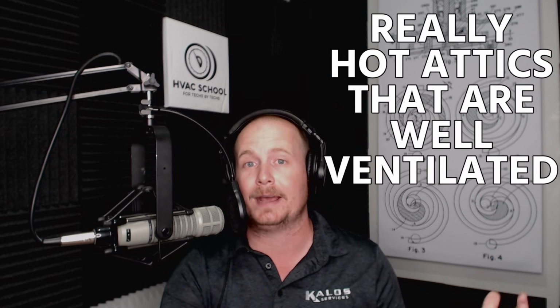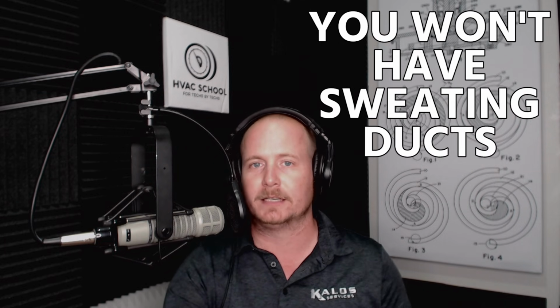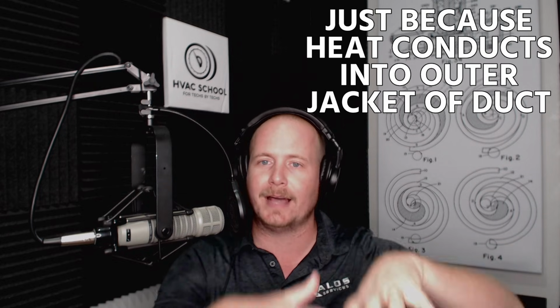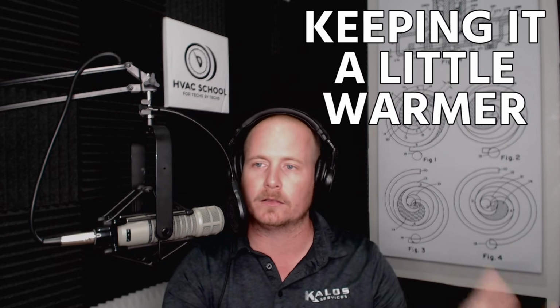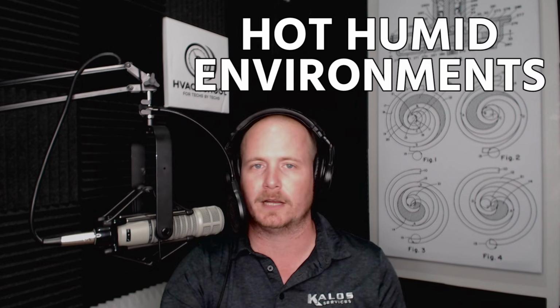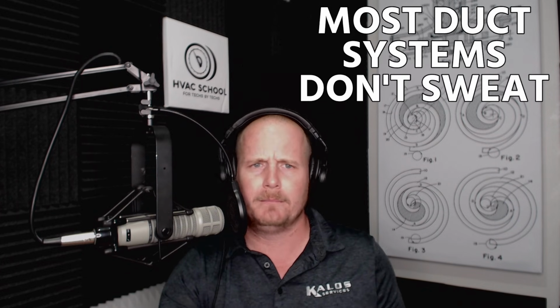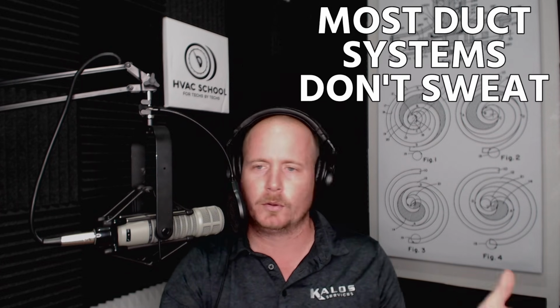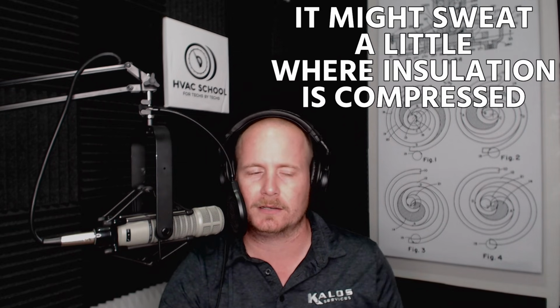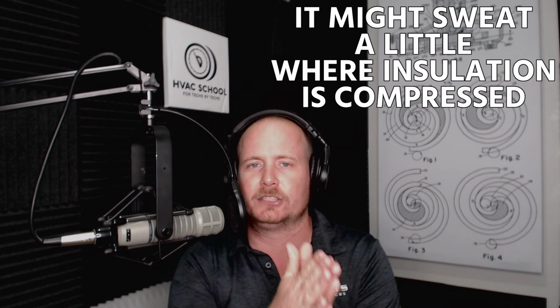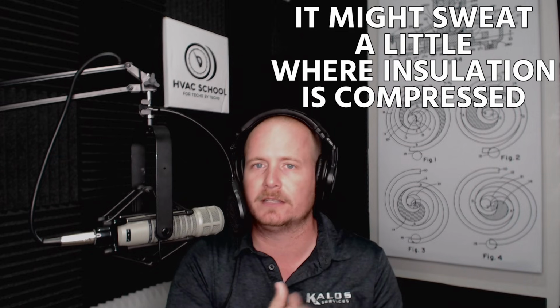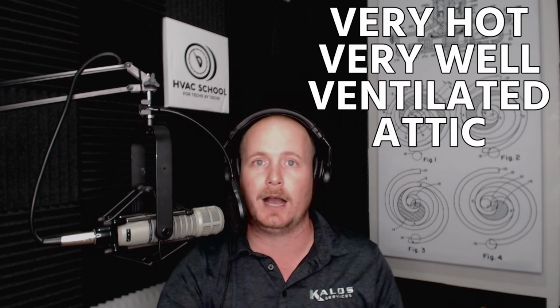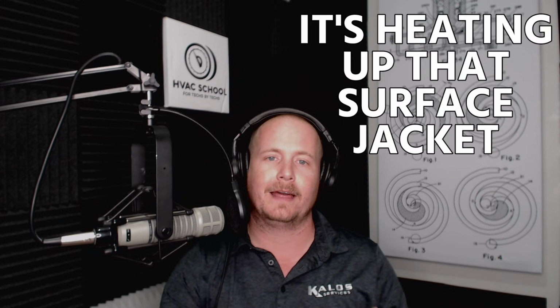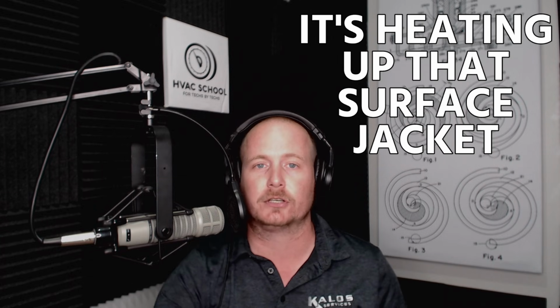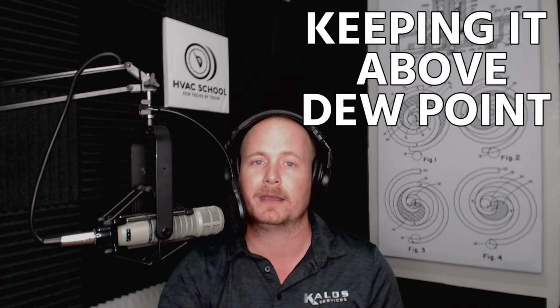Often really hot attics that are well ventilated, you won't have sweating ducts just because that heat conducts into that outer jacket of the duct itself, keeping it a little bit warmer, driving it up above dew point. And so this is why, for those of you who have worked in hot, humid environments like Florida for years, most of your duct systems don't sweat. Older equipment, most of your duct systems aren't sweating all the time. You may have some areas where the insulation is compressed that they might sweat a little bit, but generally they're not sweating. That's because you have this very hot, very well ventilated attic that now is actually heating up that surface jacket of the duct itself, keeping it above dew point.